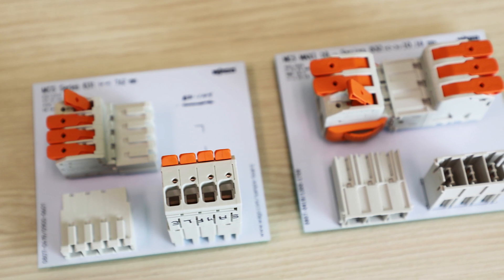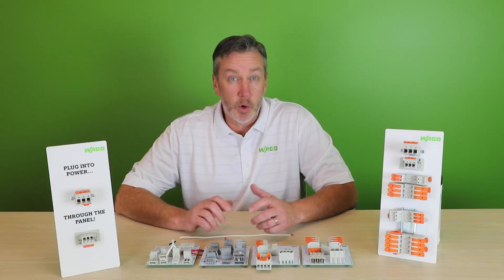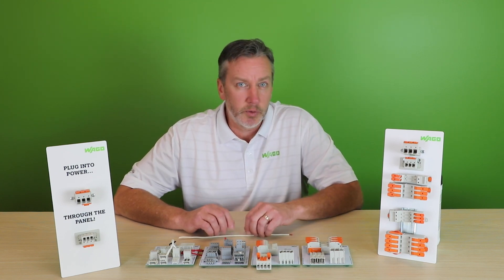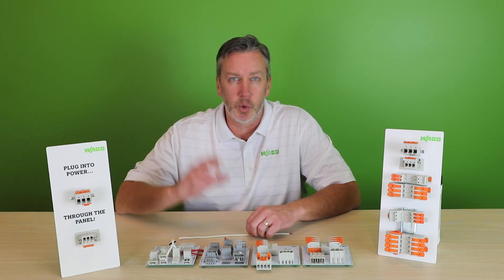It covers a wire size range of 20 to 8 gauge, with ratings up to 35 amps at 600 volts. But of course, its most significant feature can be found here in the termination area — 100% tool-free lever operation, or said another way, operable with the world's most widely available tool: your hand.